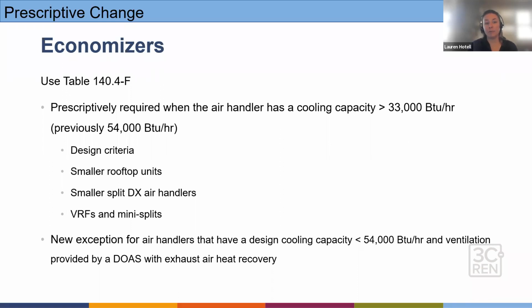There is a new exception for air handlers that have a design cooling capacity of less than 54,000 BTU per hour where ventilation is provided by a dedicated outdoor air system with exhaust heat recovery. There are a few more criteria under that, but we didn't want to include them on the slide. So if you are going to be using or qualifying for that exemption, make sure you take a look.